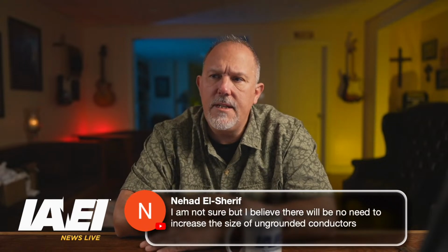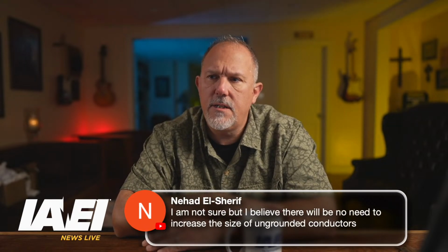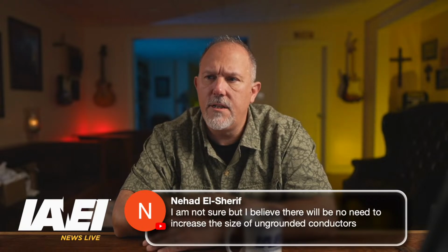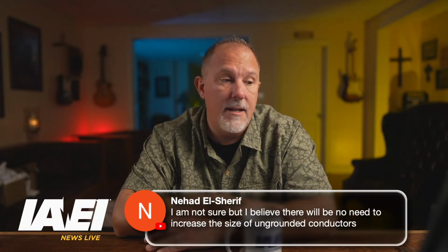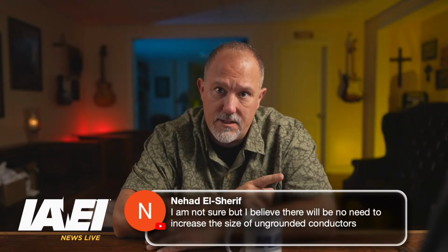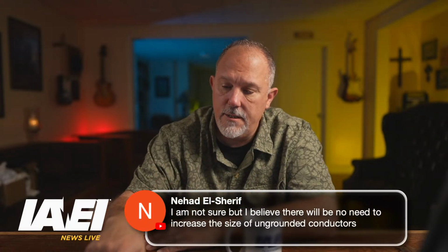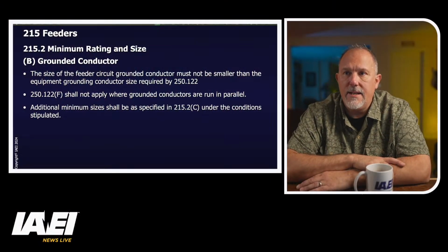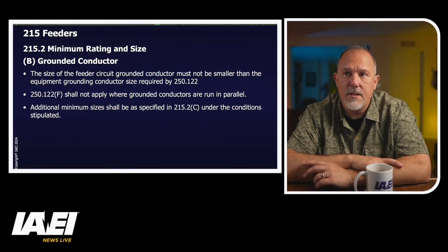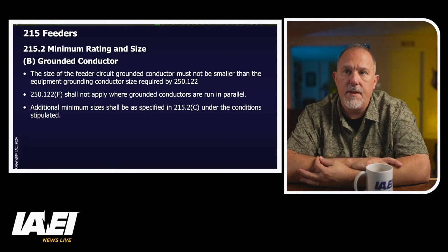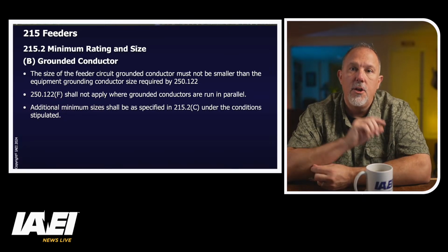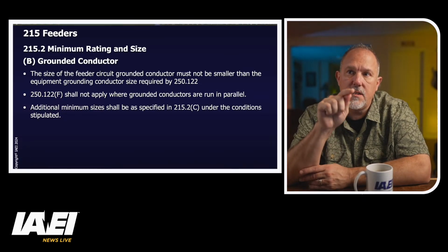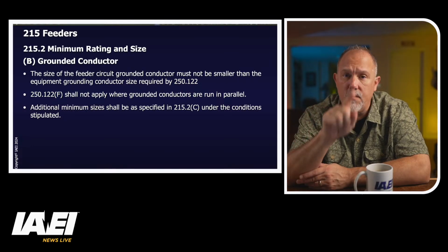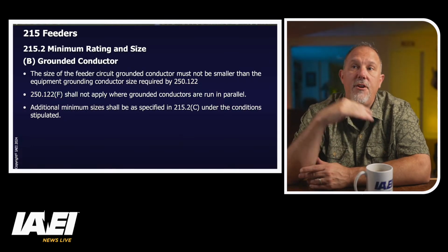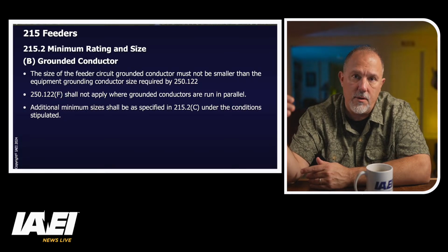I'm not sure, but I believe there will be no need to increase the size of the ungrounded conductors. But here's the thing. Based upon this section, Nihad, it says the size of the feeder circuit grounded conductor must not be smaller than the equipment grounding conductor sized by 250.122. So if I have to increase the equipment grounding conductor for the reasons that you're saying, and not because of 250.122, then I would agree with you.